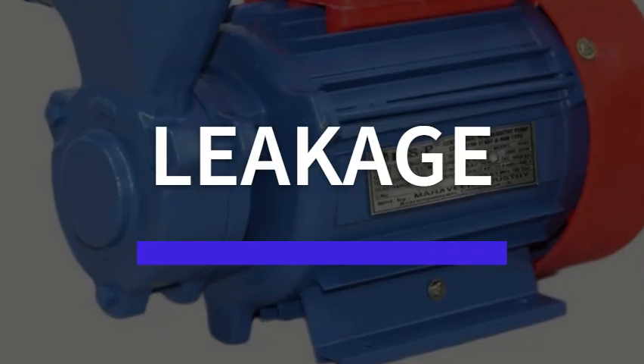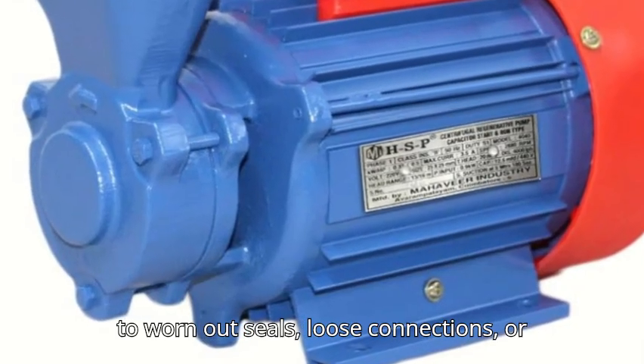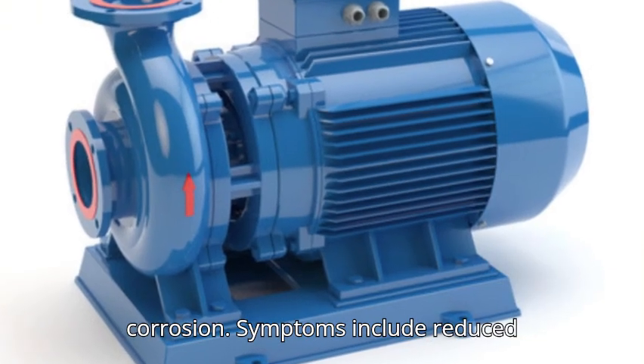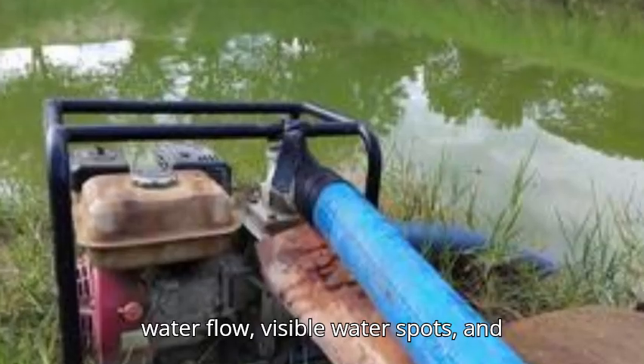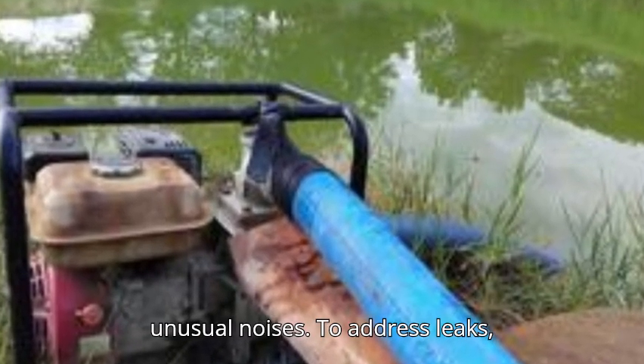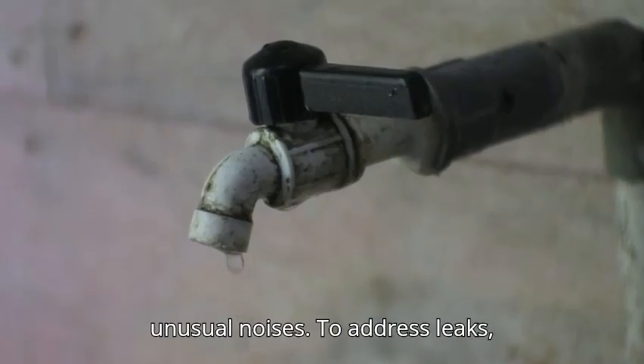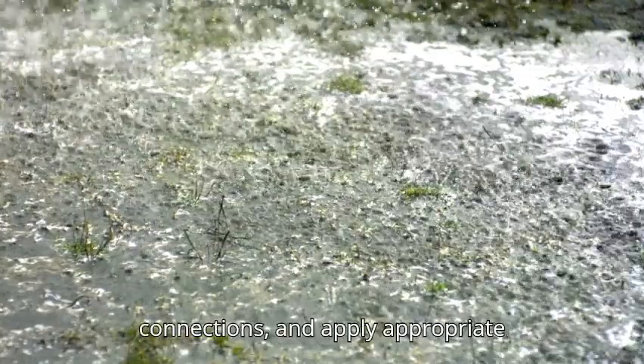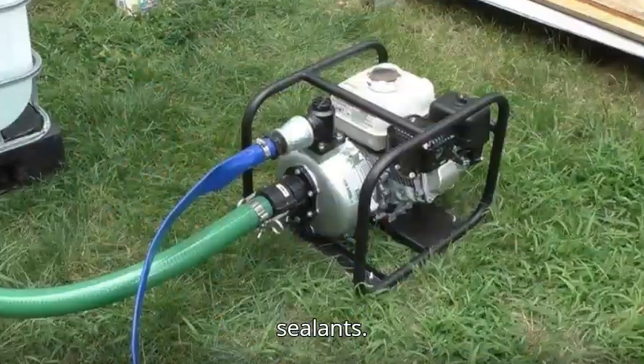Leakage. Leaks can occur due to worn-out seals, loose connections, or corrosion. Symptoms include reduced water flow, visible water spots, and unusual noises. To address leaks, replace damaged parts, tighten connections, and apply appropriate sealants.